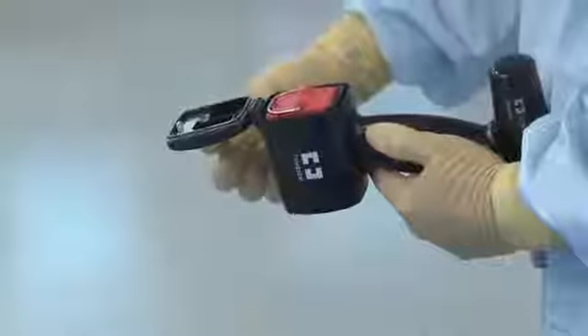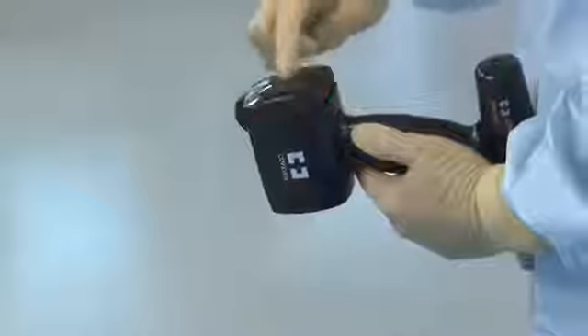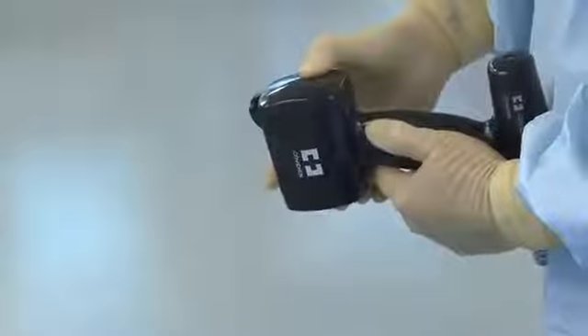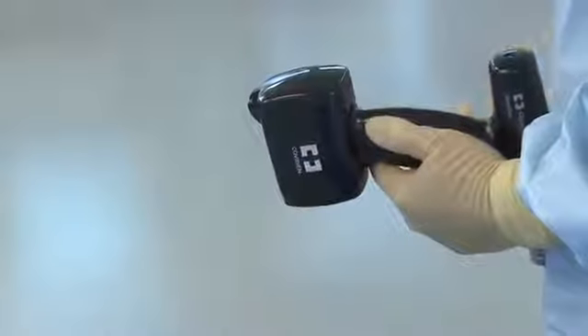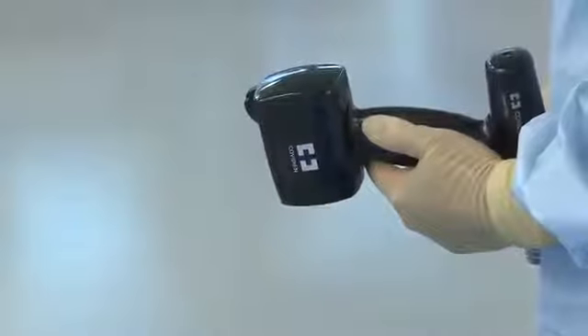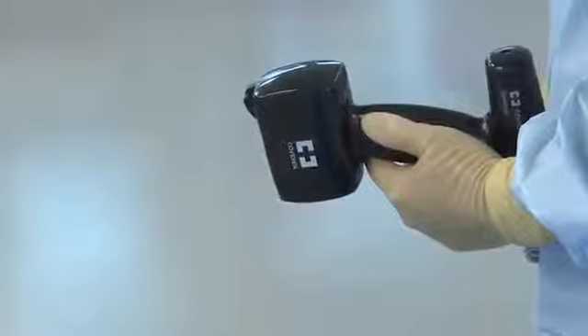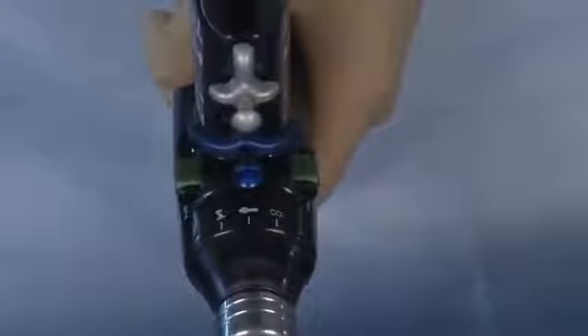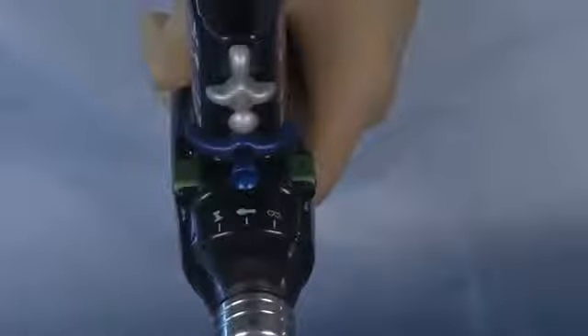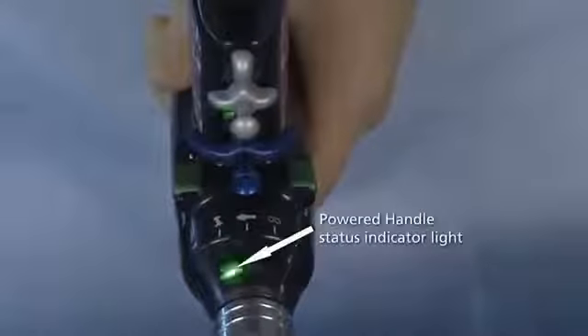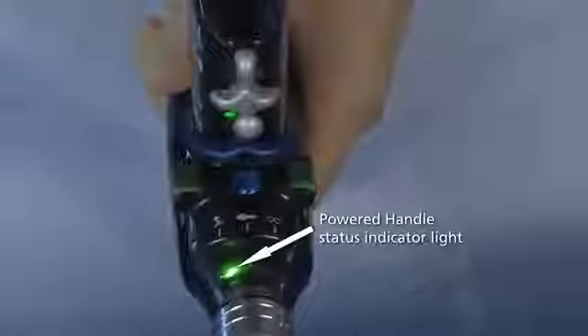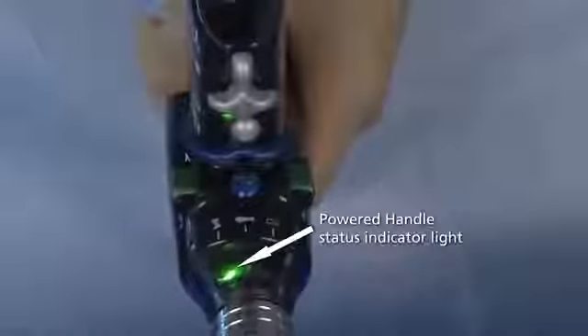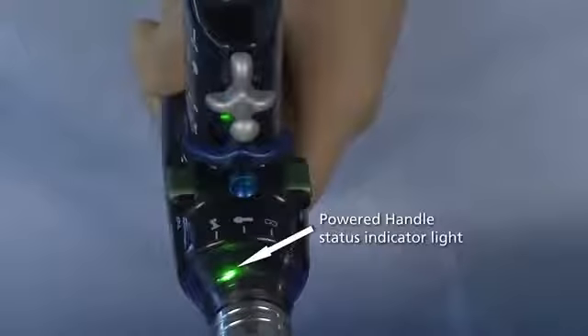Taking care not to touch the non-sterile battery pack, the scrubbed person closes the battery compartment door. Tactile feedback and an audible click confirm that the battery compartment door is fully latched. The iDrive Ultra powered handle will automatically perform a self-test. The powered handle status indicator light will steadily flash with a green color while the self-test is in progress. The indicator will show solid green when the self-test is complete and the handle is ready for the Endo-GIA adapter attachment.